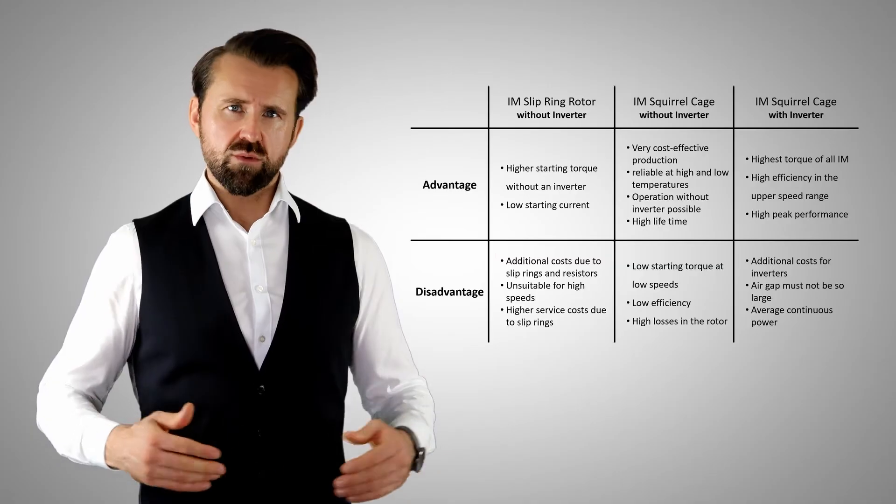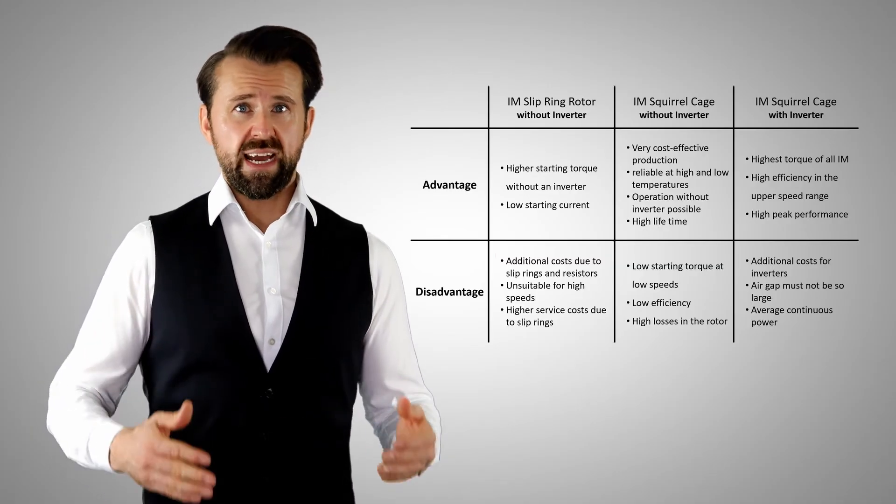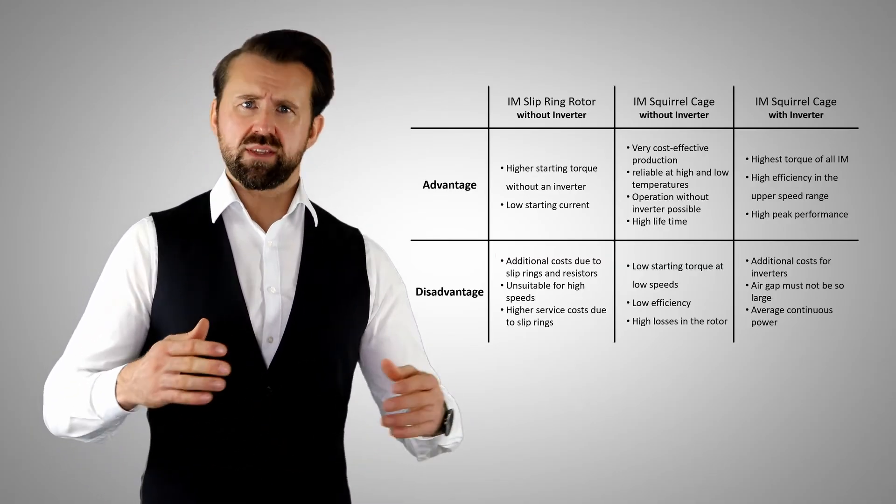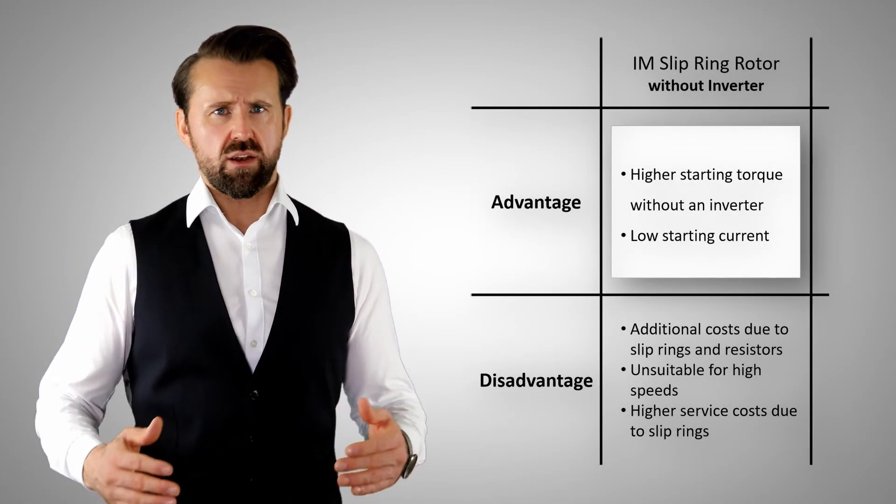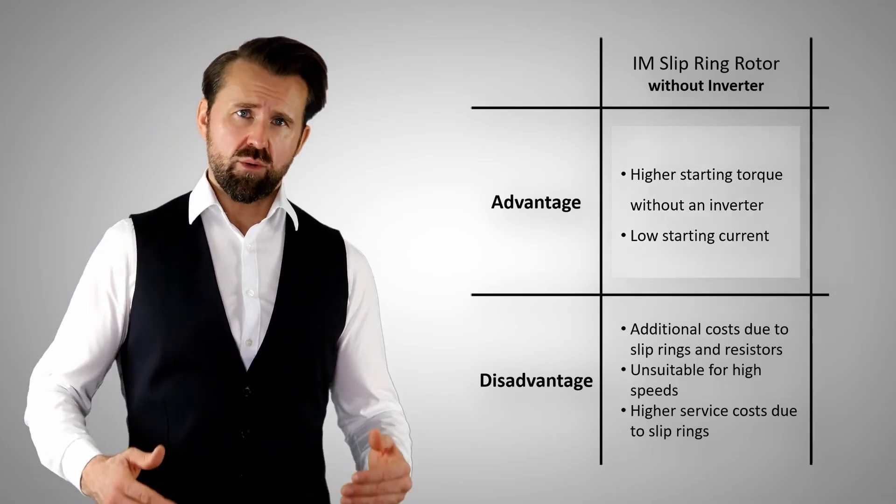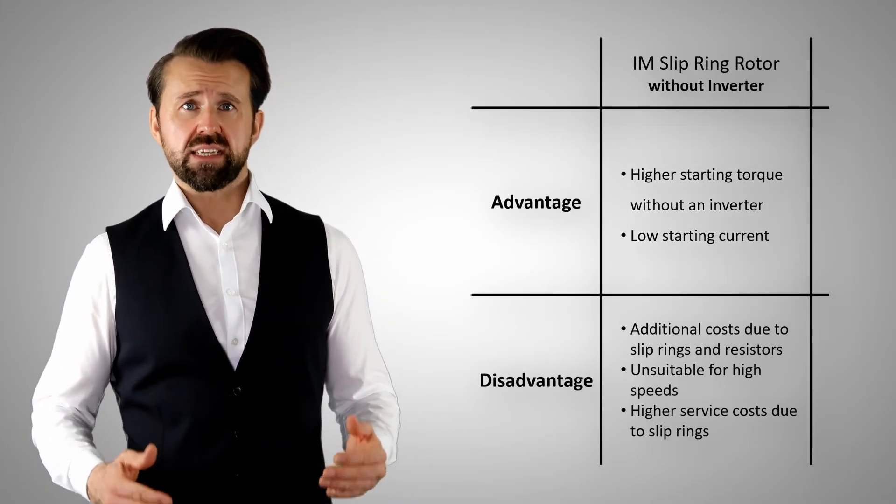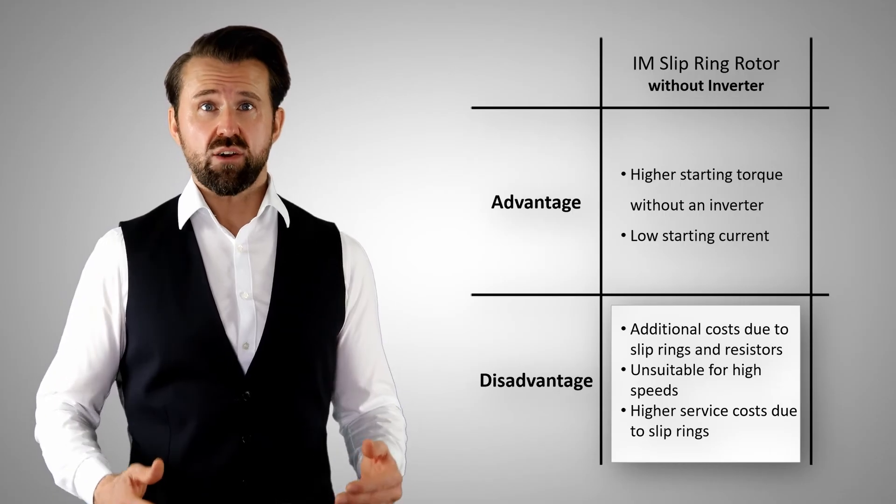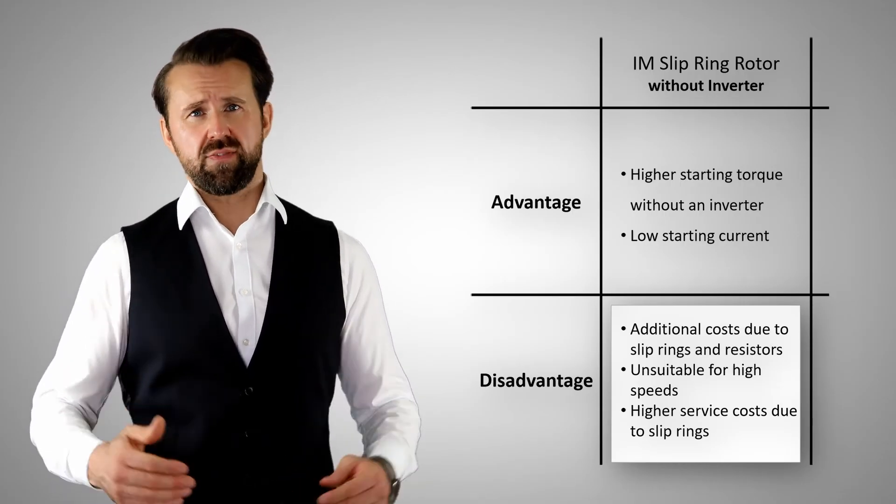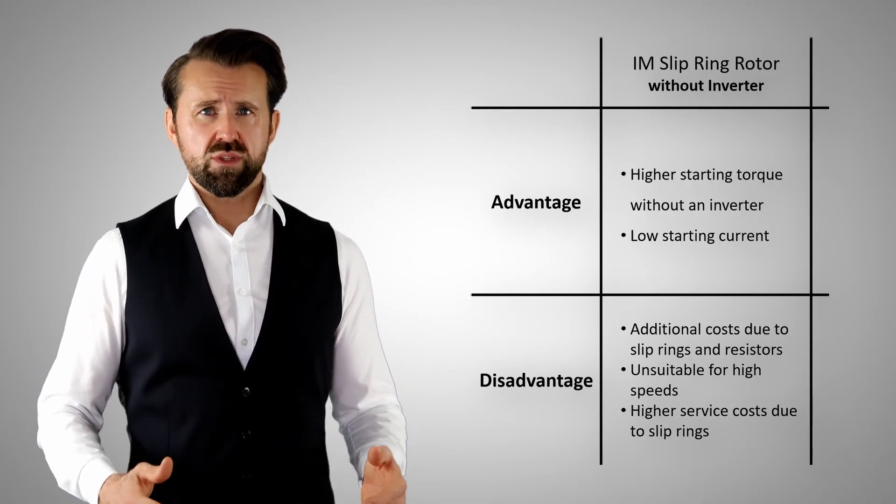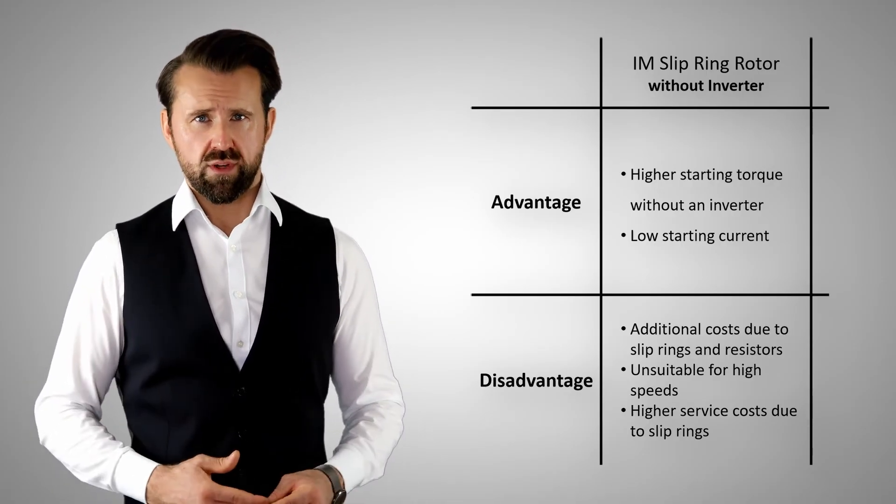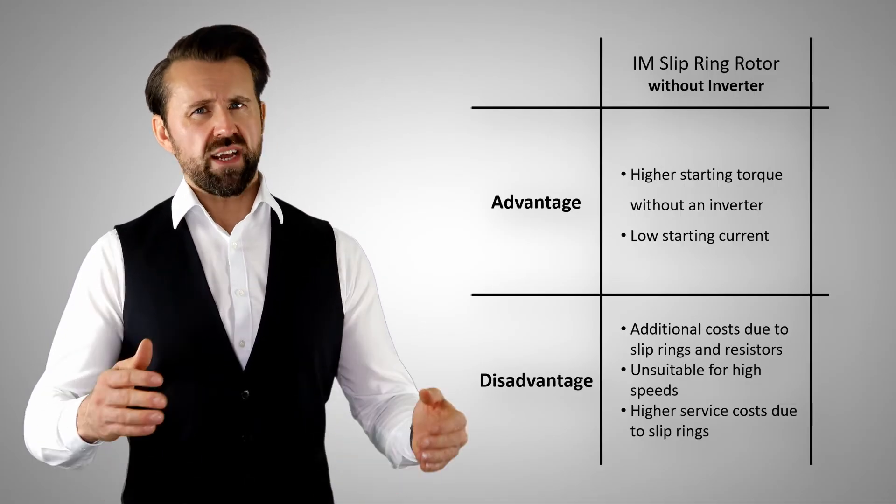Now let's take a look at the advantages and disadvantages of induction motors with slip ring rotor and with squirrel cage rotor, with and without an inverter. The main advantage of induction motors with slip rings is the higher torque in the lower speed range and the lower starting current. However, the additional cost of the slip rings and also the production of the rotor with the windings is significant. Therefore, today the slip ring rotor is only used for very large electrical motors where the inverter would be too expensive.